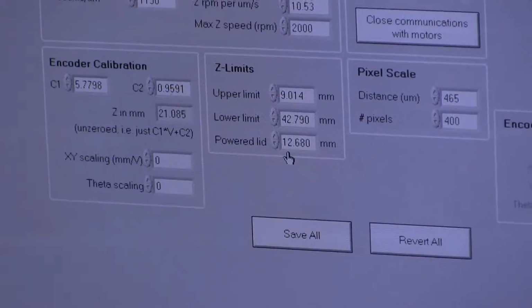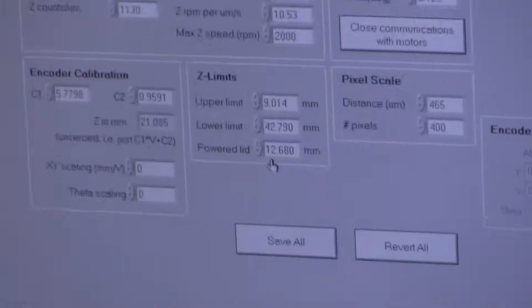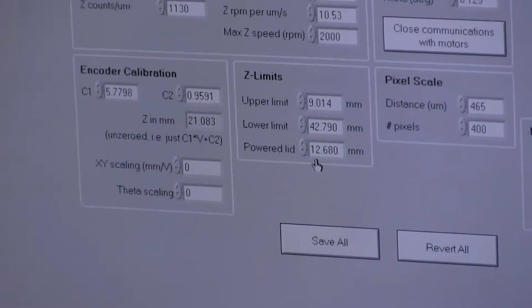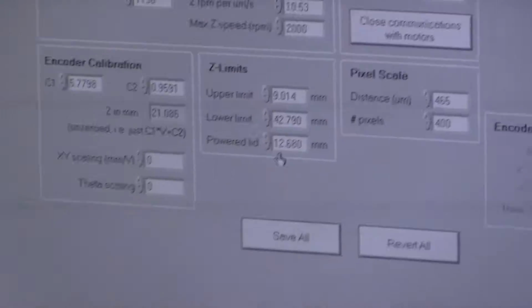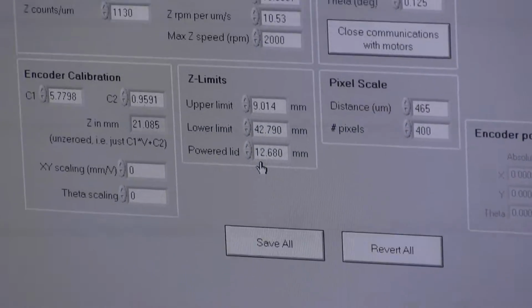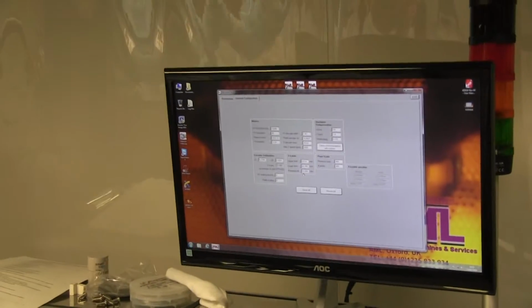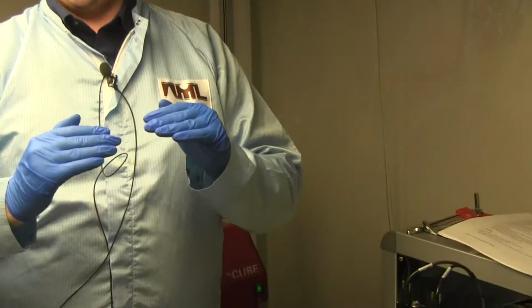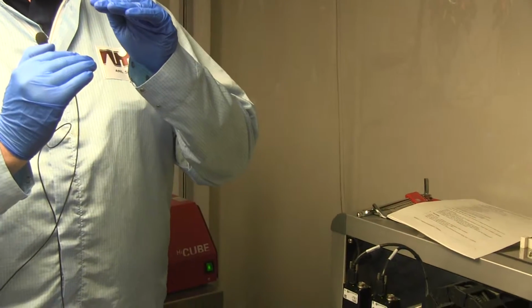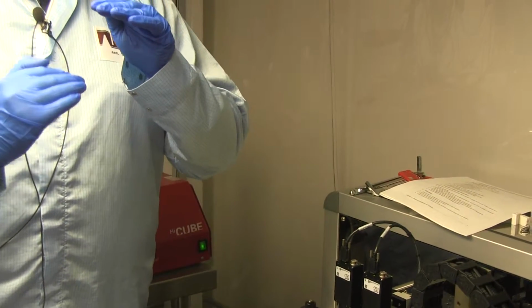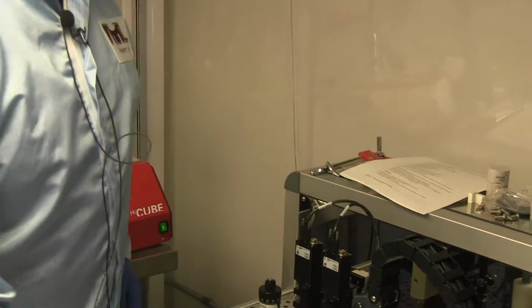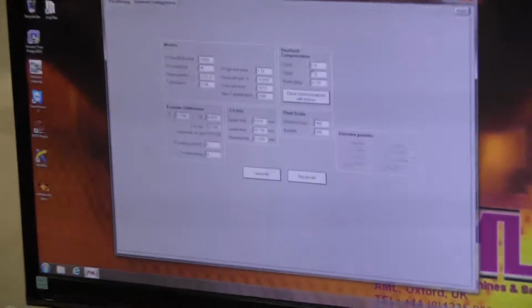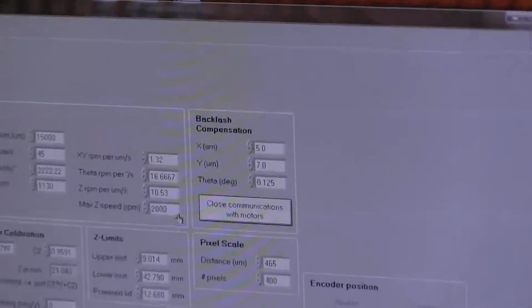The lid is interlocked, so you can only open or close it when it's safe to do so. One of the conditions required for it to be safe is that the platens are separated, because in actual fact the lower platen can overlap the position of the upper platen, and if it was higher than the upper platen, if you try to close the lid, they're going to crash. So it forces you to have the lower platen lowered sufficiently to make it safe, and that's determined with this number. Backlash compensation is not really relevant on your system.